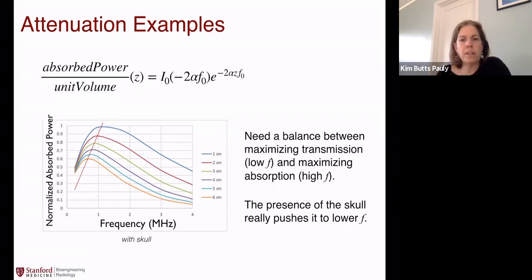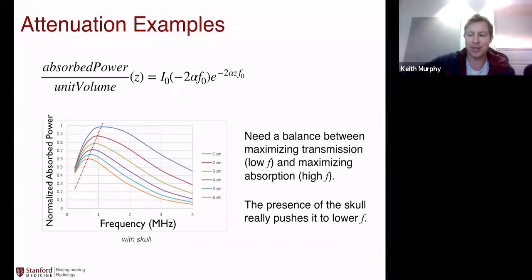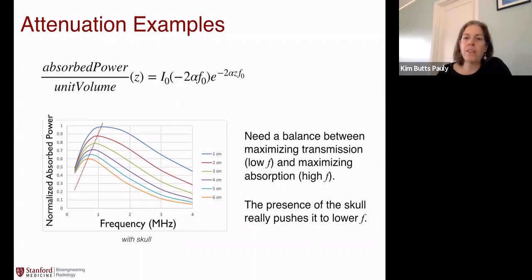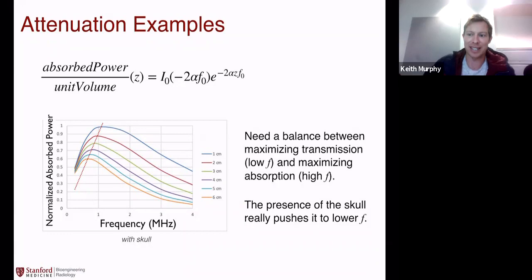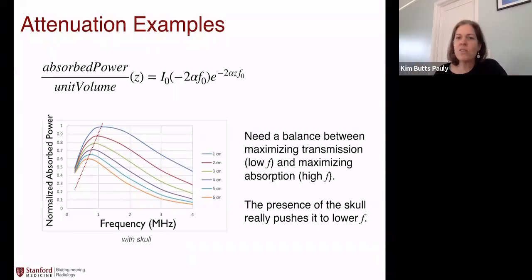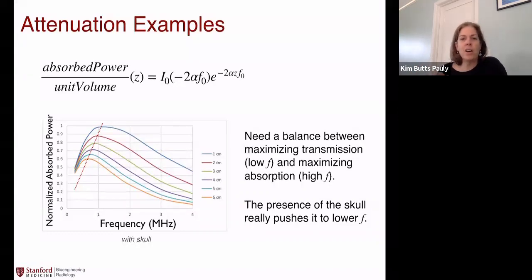What frequency do you operate at? It depends on the transducer you're looking at, but I always end up somewhere in the 600s for most of our projects. It depends on the transducers — you choose a transducer based on the frequency you want. It's even far more complicated than this simple two-component system. There are other factors that play a role — the focal spot size, for example. The higher frequency you go, the smaller the focal spot size.